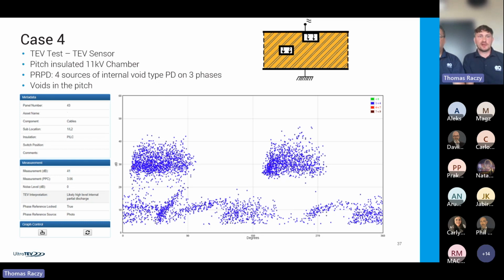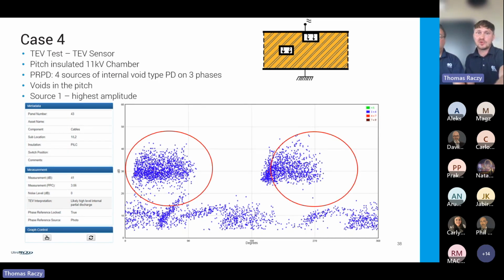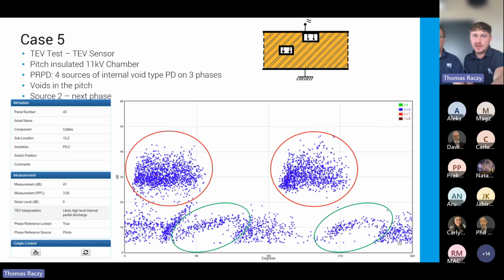Again, it's a pitch-filled 11 kV chamber, and there's a lot of things actually happening here on that screen. So we've got at least 4 sources of internal PD suspected on different phases as well. The first most obvious would be that group highlighted here with the red circles. It's quite high magnitude discharge, and you can see it's very much different to another group. You can see now clearly there's a phase offset between the red and green group, which obviously indicates that those discharges actually occur on separate phases.